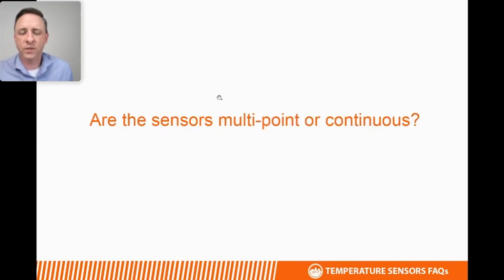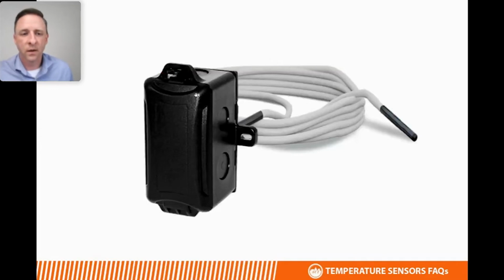Are the averaging sensors multi-point or continuous? And the answer is both. For thermistors and for 1K nickel RTDs, they're multi-point. So that means that over the length of the element, there will be multiple sensing elements that are wired series parallel to get an average of the multiple sensor readings. All of our platinum RTDs and transmitters are continuous, and that means there's one thin film sensing element that's stretched out across the entire length of that element, whether it be 12, 24, 50 feet or longer in length.